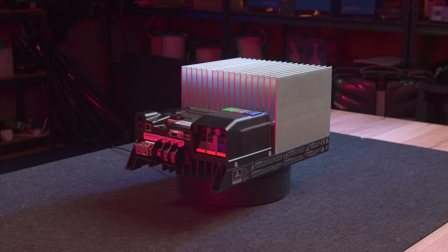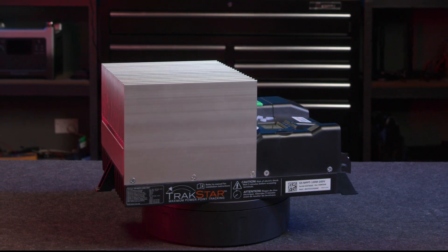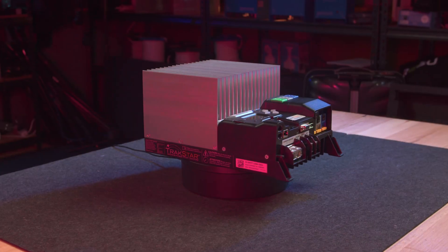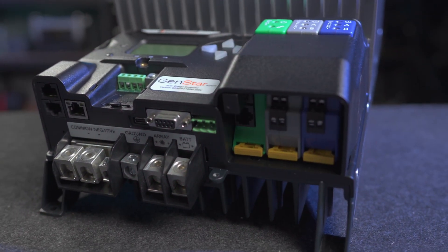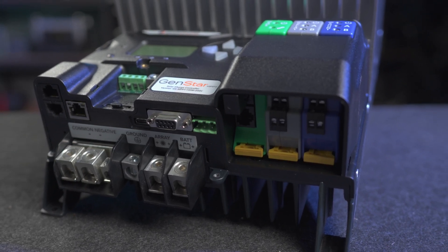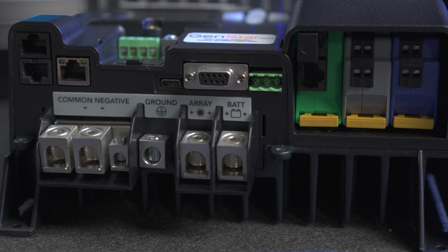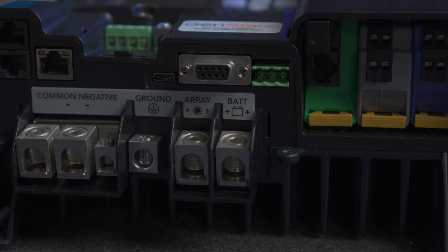Future Glenn here, just a few details I missed in the initial recording. With the ready shunt, it can be supplied with or without an actual current measuring shunt itself — so if you're ordering one and you've already got a shunt, you don't need it, but if you haven't you'd want to order one. The Ready BMS is currently compatible with Pylon Tech and the Discover smart lithium batteries, and I suspect more will follow as testing is completed. You can also insert an SD card into the slot, which really simplifies commissioning of the Genstar — it can effectively be cloned so you can take the SD card out of one unit and pop it into another, and it automatically brings it to the same settings. That's a great feature if you've got a larger installation or a rinse-and-repeat design.